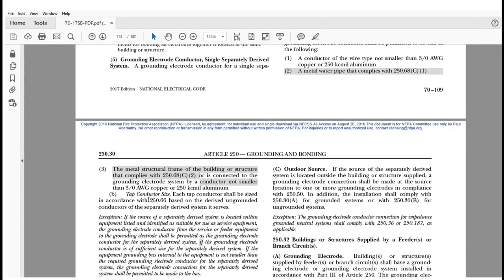250.30(A)(6)(a). If I'm an electrician, what I take away from this change is that now in a high-rise building or multi-story building where I have multiple separately derived systems, I can run a common wire like I always did before, that is, as long as it is 3/0 copper or 250 kcmil aluminum or larger, and I can take my taps to it in order to make that connection to the grounded point on those separately derived systems, where the system bonding jumper is, of course. But now I can utilize a metal water pipe for this application, and I have a little more clarity on the structural steel. It's not so much about the portion in 250.52 about in the earth, it's about the extension of that metal structural frame as an actual conductor. Okay? And that's what we're talking about here.